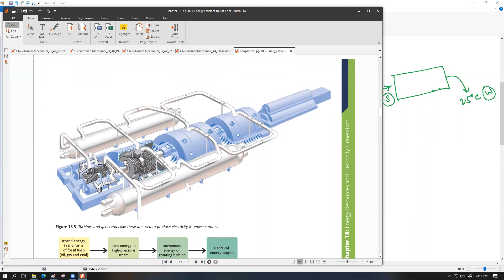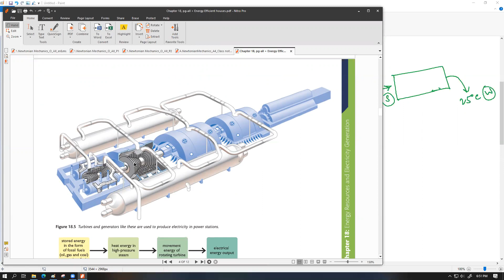If this turbine, after absorbing heat energy from the steam, could give out water at 25 degrees Celsius, then we could say that the turbine absorbed all the heat this water absorbed in this process. But that doesn't happen. The turbine cannot ever convert that steam into liquid water. Turbines are essentially designed to operate only with the gaseous state of water, which means it can only operate with steam. At best, it can absorb enough heat so that the output is 100 degrees Celsius steam.